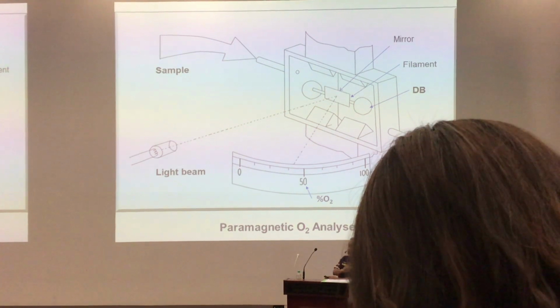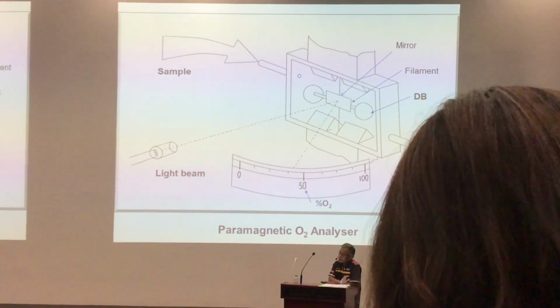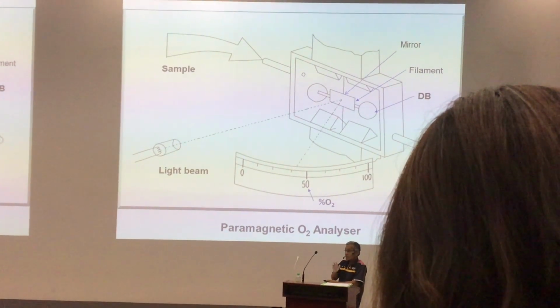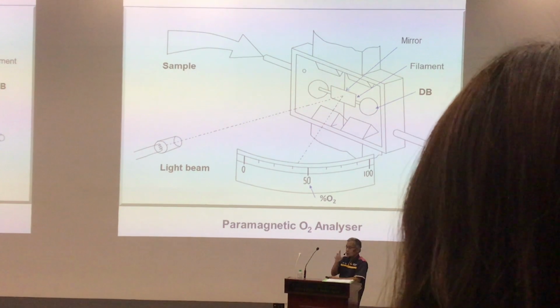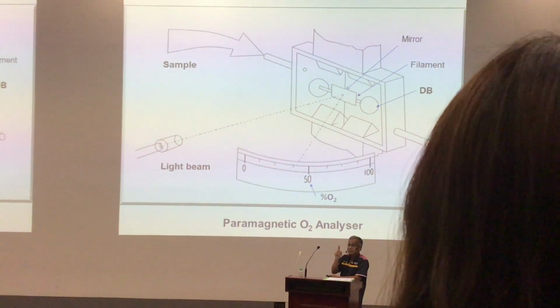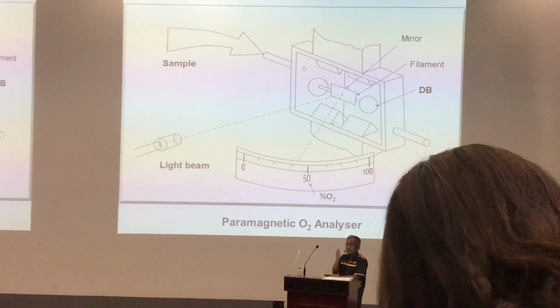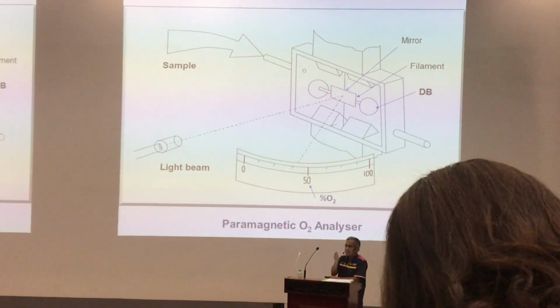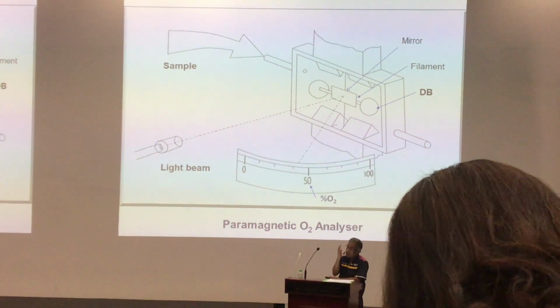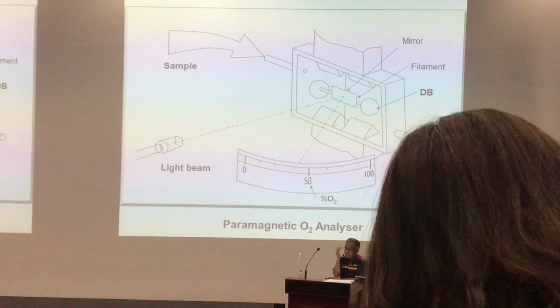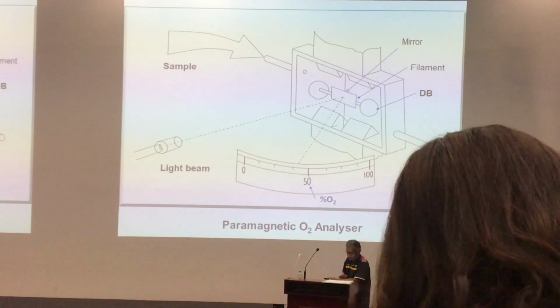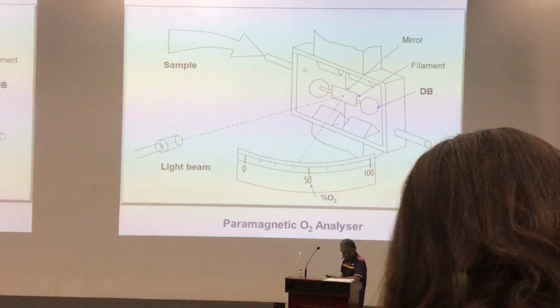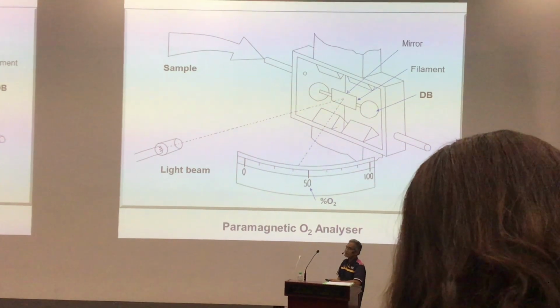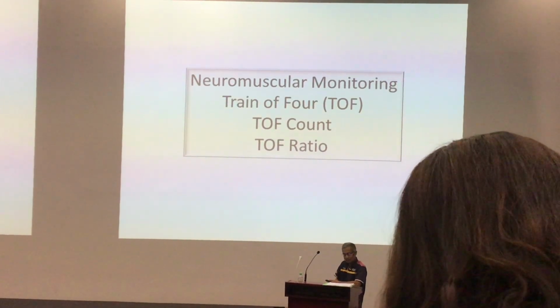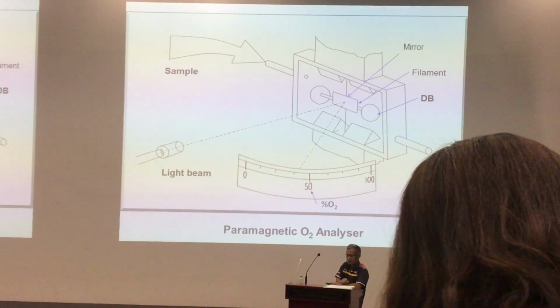But it's not meant for anesthesia. Okay, this is for ICU. ICU is important because for ICU ventilators, they use many paramagnetic oxygen analyzers. Which means the FiO2 measured by the ventilator, Drager or Hamilton, whatever ventilator you use, they use a paramagnetic oxygen analyzer to measure the FiO2 delivered to you. So they don't use a fuel cell, they don't use a mass spectrometer, they use a paramagnetic oxygen analyzer based on the paramagnetic property of the gas. You just mention a paramagnetic oxygen analyzer for ICU ventilator. So for detail, maybe you draw this diagram, you are a superhero.